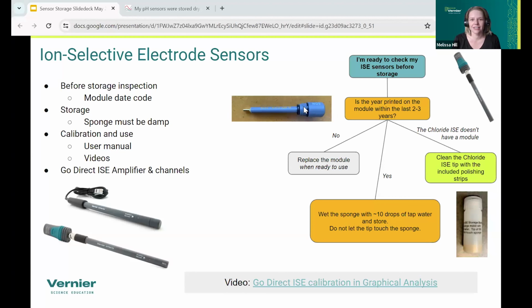And it's good to do that before you store it, because then you have to order one and it takes a couple weeks for us to get it to you. So we like you to look at that more than the day before you want to use it. Then if the module is within 2 to 3 years, you're getting good data with it, you didn't have any problems, it doesn't have that sticky note that says doesn't work on it, you just make sure that you wet there's a sponge that comes in the storage solution bottle or storage bottle, and you just want to wet it with about 10 drops of tap water and put it on the edge of the ISE and store it.